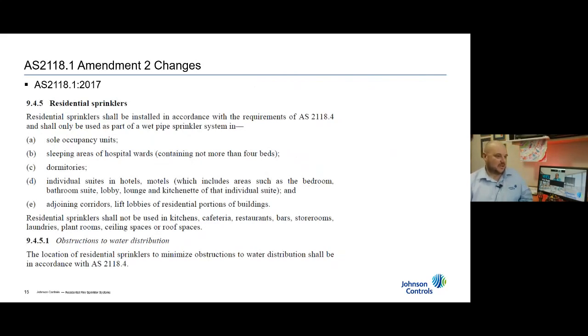One of the other changes is clause 9.4.5 in the existing 2118.1, and you'll see there that it references residential sprinklers, but they shall be used in accordance with the requirements of 2118.4 and shall only be used as part of a wet pipe sprinkler, and so on. Then it talks about obstructions to water distribution in 9.4.5.1. The intent here was that if you have a floor which is residential, you design that floor to 2118.4 for the obstructions really only. That was the intent.